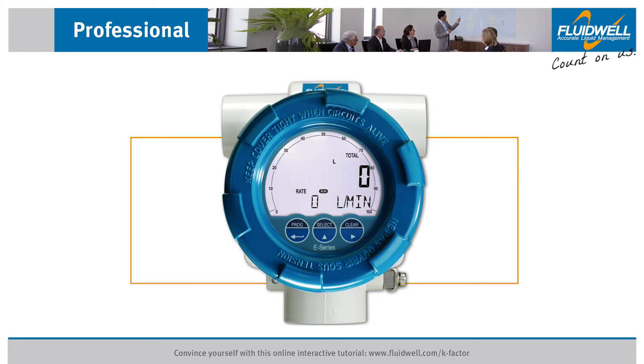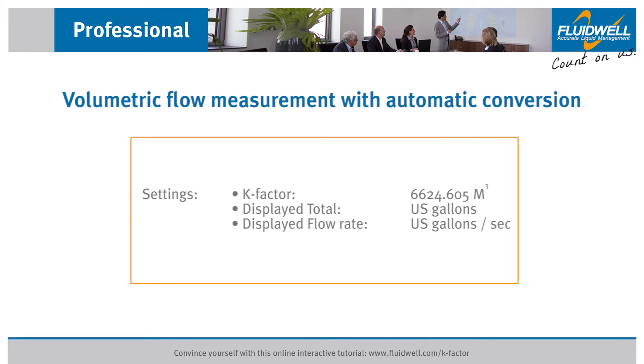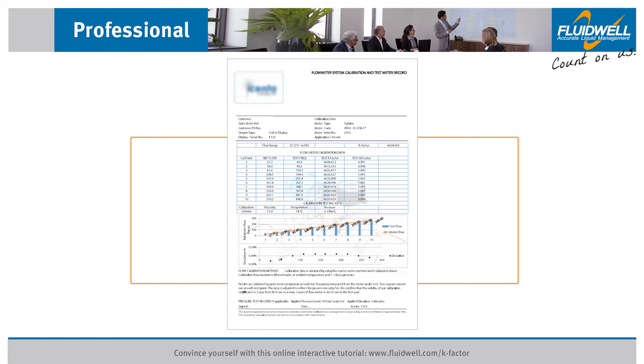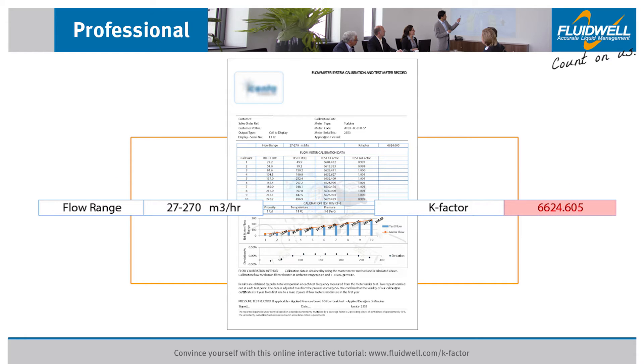The k-factor setting should be configured before installation to ensure correct measurements in any situation. In this tutorial we will set the k-factor for volumetric flow measurement with automatic conversion and configure the settings to display the volumetric total and flow rate. Before we set up the k-factor we need to identify this number as provided by the flow meter manufacturer. In this example that is 6624.605 and the measurement unit is cubic meters.